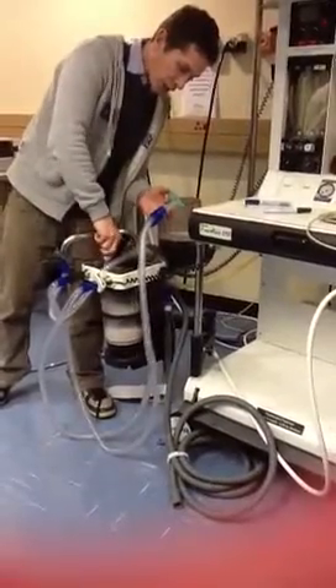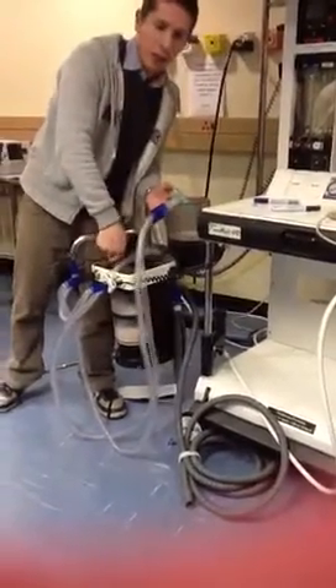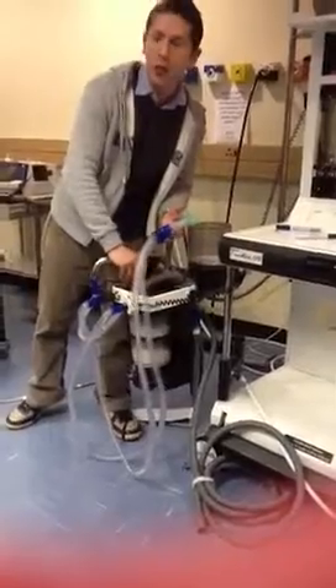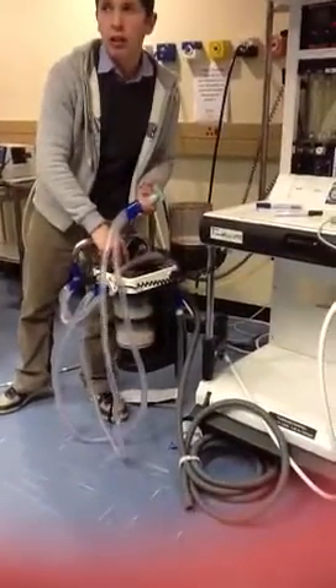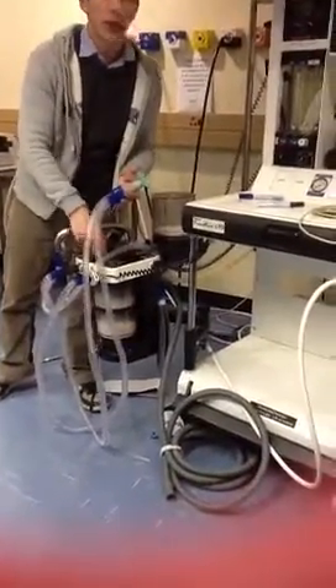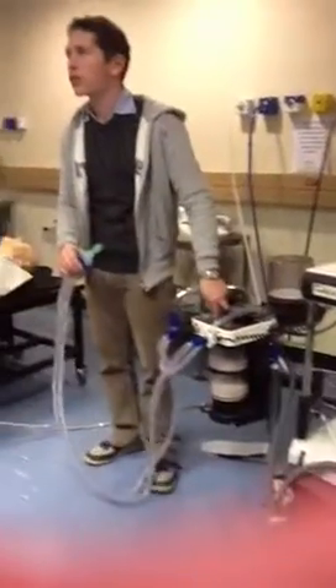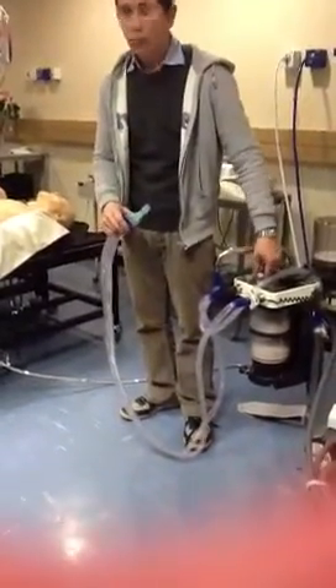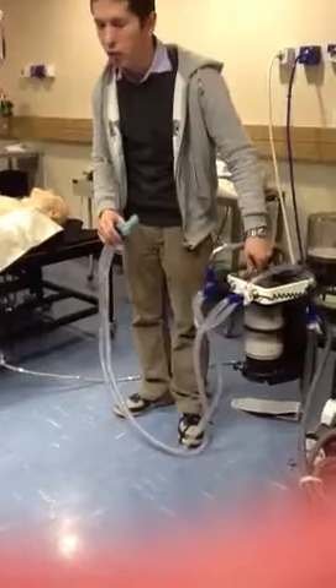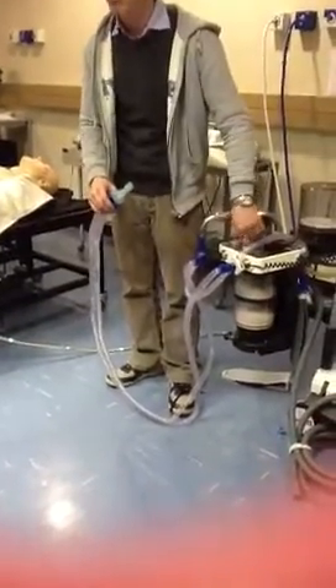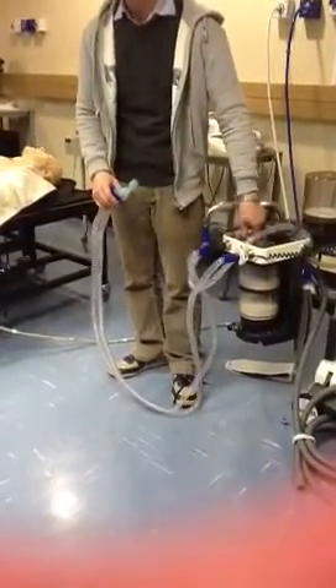Yeah, if you work somewhere you just have to make sure how the oxygen analyzer works. And if the oxygen analyzer is dependent on you calibrating it once a day, then you just have to calibrate it in the morning. Okay. The Fabius machines you still have to calibrate, so we calibrate in theatre, but the Primus machines, they do it automatically.